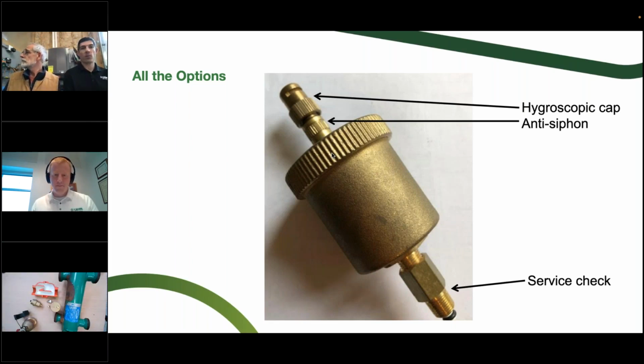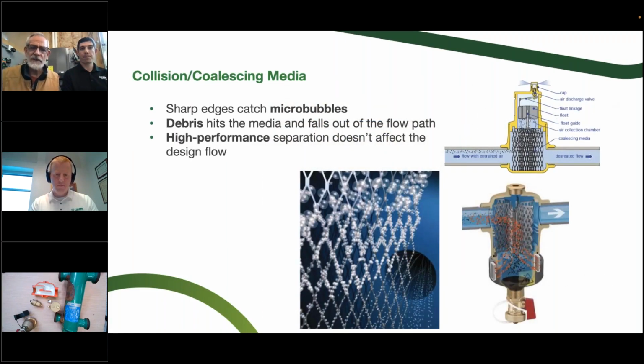And that's what we were getting at with, I thought I had everything installed right. I've got proper air and dirt separation. Why do I still have an air issue? That anti-siphon cap may be a good troubleshooting thing to have one of in your truck as well. And I think Mack said it does fit a lot of the other vents. I know it won't fit a Maid-O'-Mist. That's got a regular tire thread, like the cap on your tires. But I know a lot of the other valves have that same thread, so you'd have to try and see.